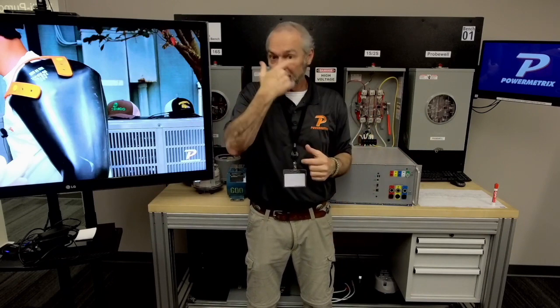It could be different at your utility, so they'll tell you the specifics, but this is just for folks new to this watching - there are definitely classifications for gloves depending on where you are in the system and on the circuit. The outside of that pad mount transformer, your utility could have a different glove rating than going inside. Also consider the other PPE - sleeves, face shield, safety glasses. Outside, you may only need safety glasses, a hard hat, and the Class A gloves.